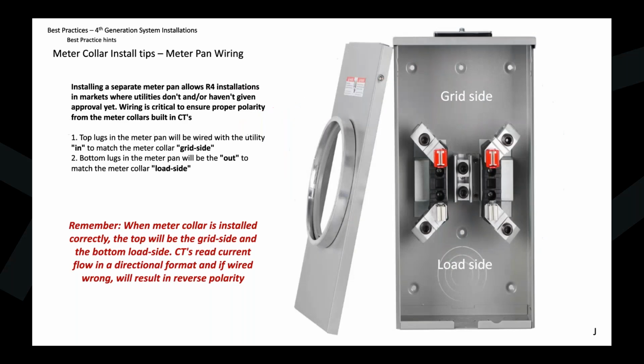So this is going to be a common installation for areas where we don't have meter collar approval, or we're still going through the testing and waiting for that approval, where we'll have to put an external pan. And the learning here is we know that the grid side of the actual meter collar is at the top and the load side at the bottom.